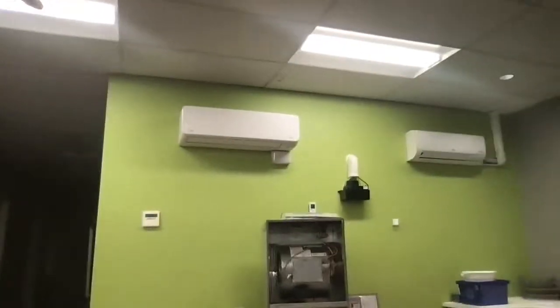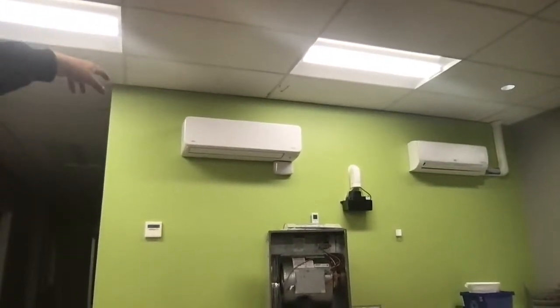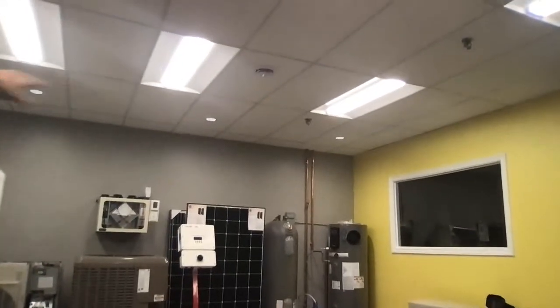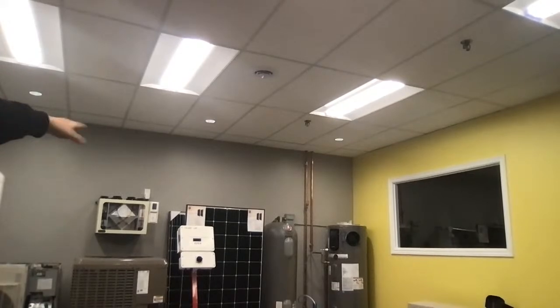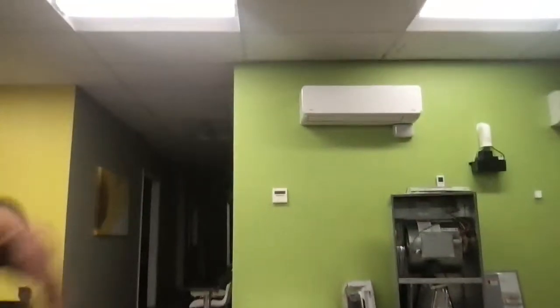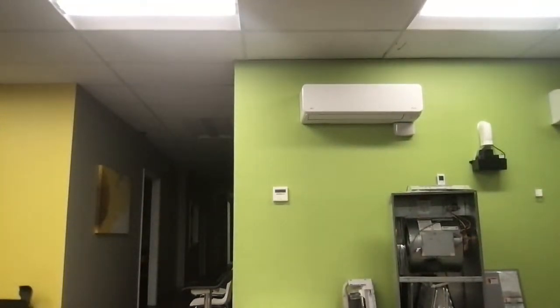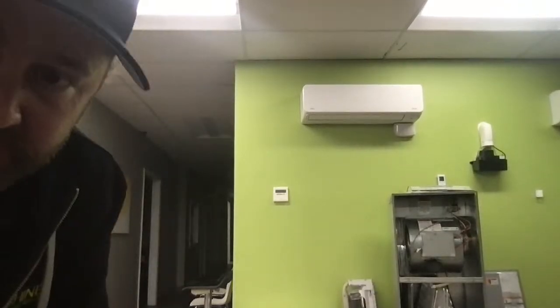That 1,500 CFM would handle a whole 2,000 square foot house. Even the mini splits put out 550 cubic feet per minute, which is still a huge amount of air. Air exchangers, by comparison, only run about 100 cubic feet per minute, so they just don't have the capacity. You're talking 5 to 10 times the airflow difference, depending on what you need.